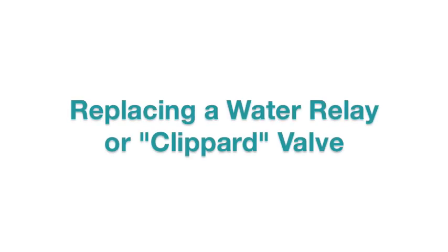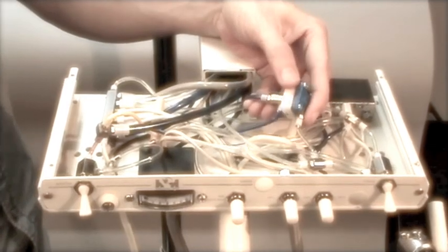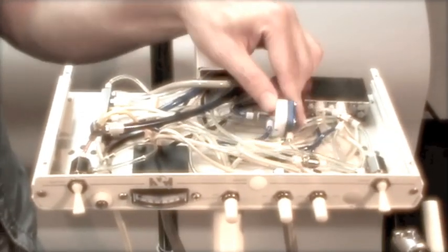We often get calls from doctors who experience water coolant leaks from their hand pieces. While the cause may differ in various units, most systems incorporate some form of water relay valve or clippard valve that sends water to the hand pieces. If the water does not completely shut off, the water relay valve is often the culprit.